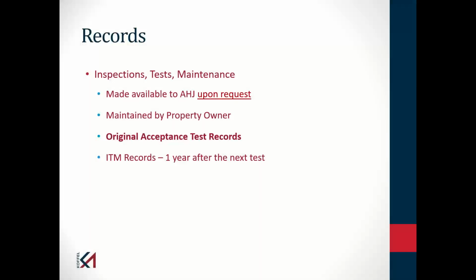And lastly, you as the owner are responsible to maintain the records. In some jurisdictions, you are required to send them to the authority having jurisdiction. In most cases, you just need to have them available upon request of the AHJ. With regard to inspection, test, and maintenance records, you are required to keep them 1 year after the next test. So anytime I walk into the building, if it's an annual test requirement, I'm likely to be able to find 3 years worth of test information.